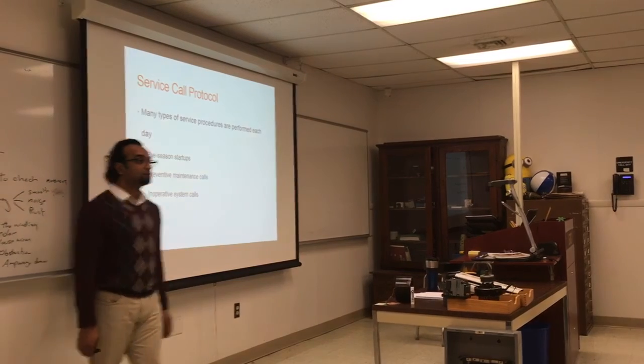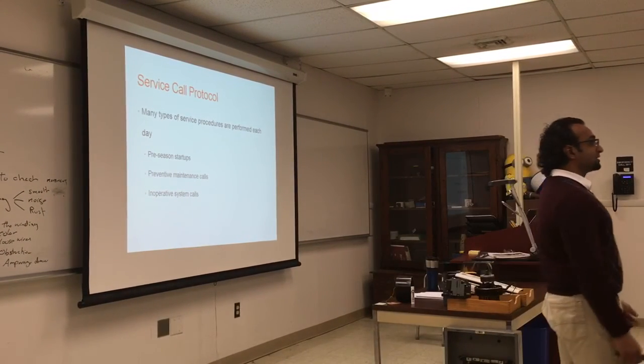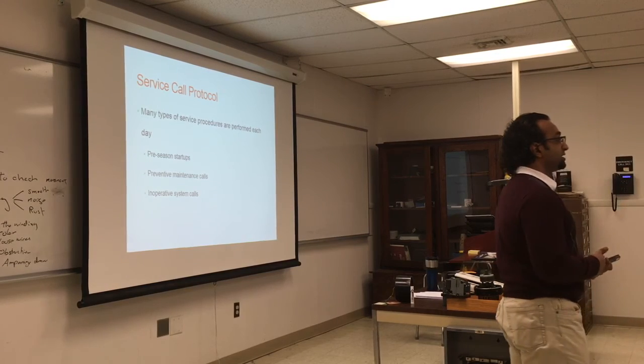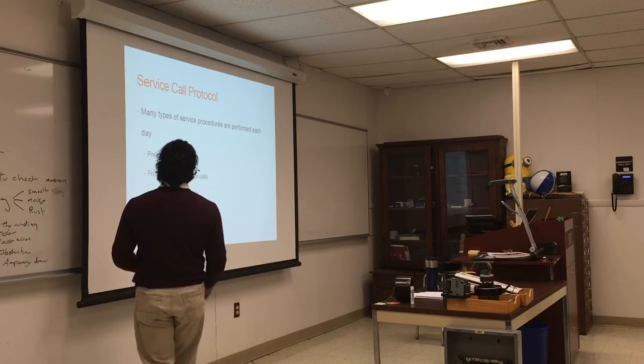So I had a service call one day on an AC, and the technician came and told me, yeah, this motor is kind of loud and it's giving off a lot of heat. I think you should order a motor and keep it on standby. Let it run until it dies, but at least you'll have a spare part, because the order sometimes takes 3 weeks, so you have something on the side. So you might want to do that as well.